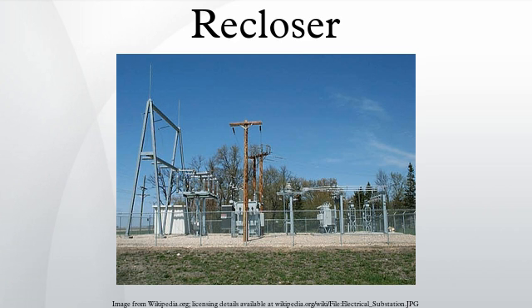This means that a single event on the grid will cut off only the section handled by the single recloser, long before the feeder station would notice a problem. A normal breaker could also be used for this role, but because they are distributed geographically throughout the grid, as opposed to being centralized at feeder stations, resetting a breaker might take considerable time. For this reason, reclosers are used to automatically reconnect after a brief interval.